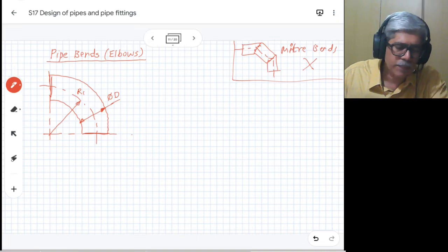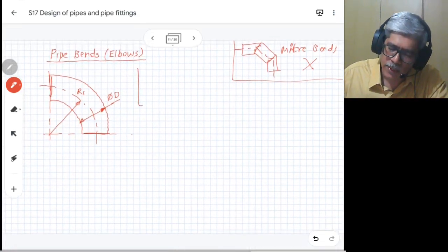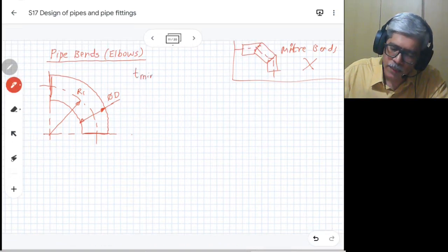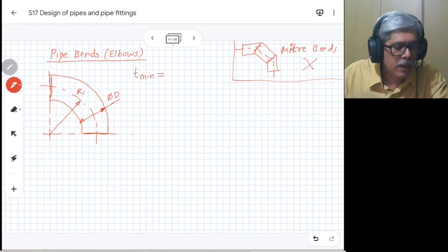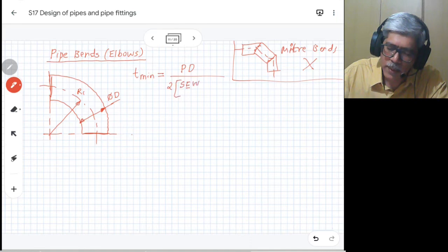The minimum thickness for this type is given as: t minimum equals P times D divided by 2 times the quantity S times E times W plus P times capital Y.